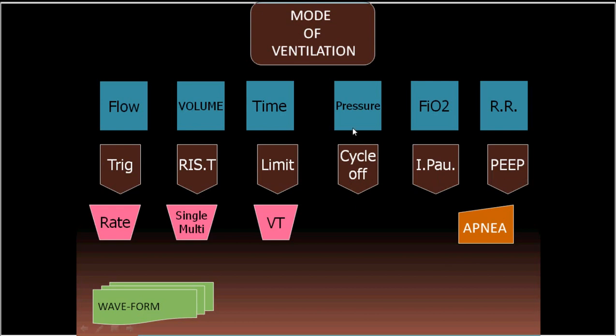This pressure is responsible for increasing the functional residual capacity by a certain level. So it acts like a PEEP, but it is not a PEEP — it is CPAP. An apnea backup mode should be given as a backup for this spontaneous mode, and the waveform is decelerating.